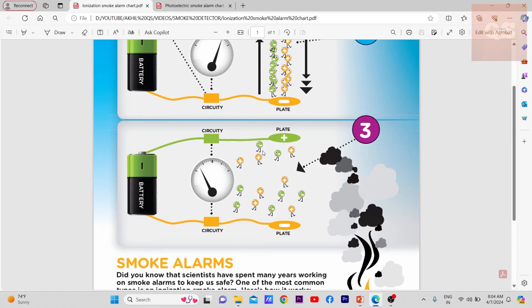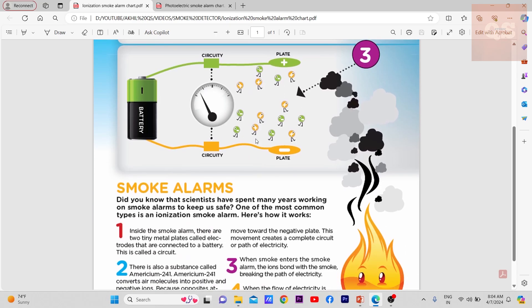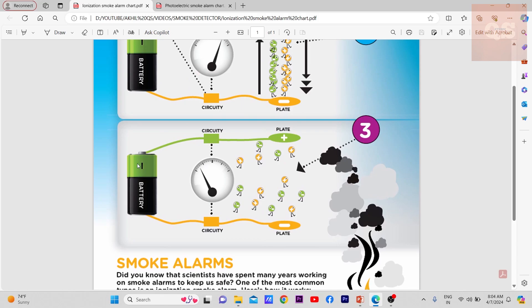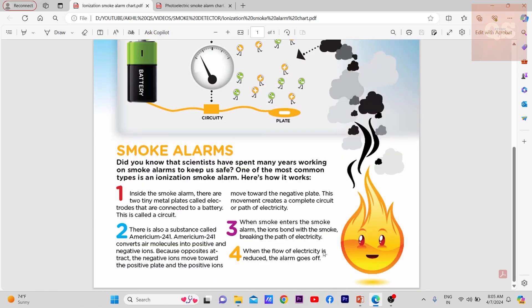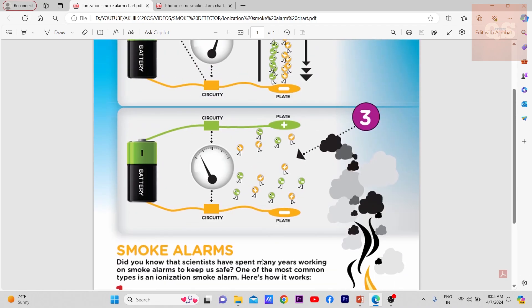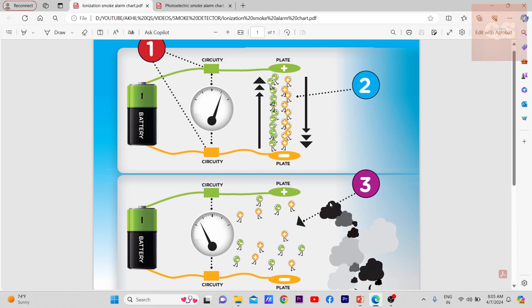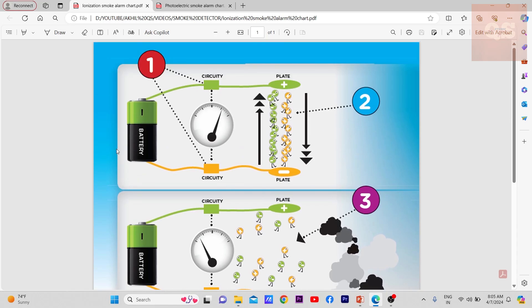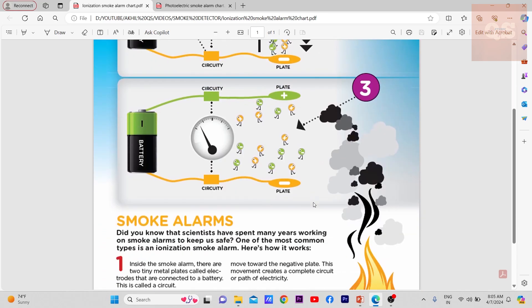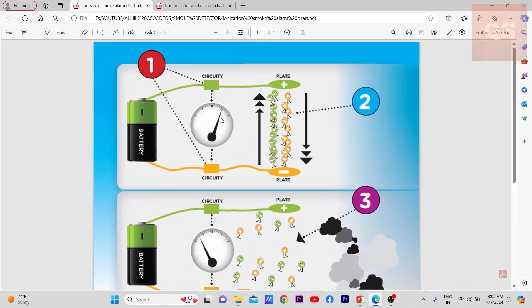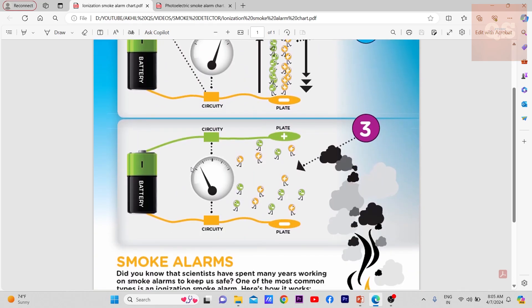When the smoke goes inside, all this path will be broken and these ions will move out. This will cause that complete circuit to break. If you see the measurement of current, when the flow of electricity is reduced, the alarm goes off. So this is the basic principle of an ionization type of smoke detector.